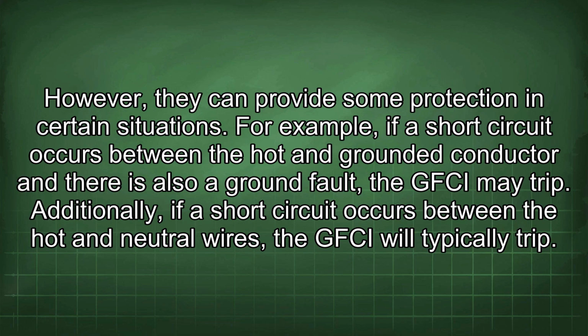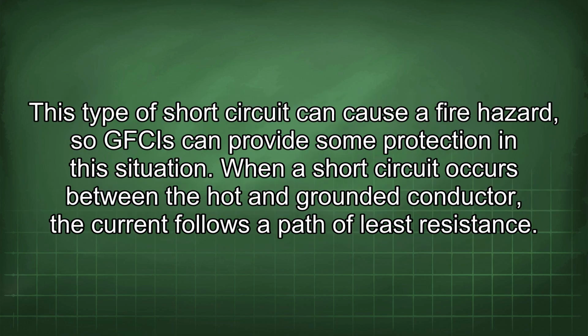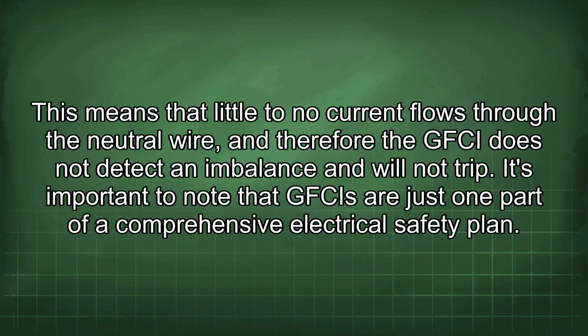For example, if a short circuit occurs between the hot and grounded conductor and there is also a ground fault, the GFCI may trip. Additionally, if a short circuit occurs between the hot and neutral wires, the GFCI will typically trip. This type of short circuit can cause a fire hazard, so GFCIs can provide some protection in this situation. When a short circuit occurs between the hot and grounded conductor, the current follows a path of least resistance. This means that little to no current flows through the neutral wire, and therefore the GFCI does not detect an imbalance and will not trip.